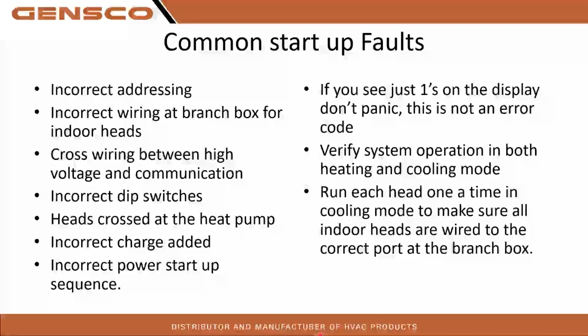Another one is the incorrect power startup sequence. I talked about that. If you see an LED or LCD display on your heat pump, and you're seeing just ones on that display, that is not an error code. Those are what we call status flags, and I'll show you what those mean in just a little bit. An actual error code is going to pop up as a 4-digit code on the heat pump: 4100, 4250, 7102. 7102 is a very common one that we see on startups. That's a code for total capacity of the system, either underconnected or overconnected. Usually when I see a 7102 on a new startup, it's because it's looking at underconnection. What people end up having issues with is incorrect wiring, cross wiring, power sequence, all those things can affect that. Condensate pumps on wall heads not wired up right, that kind of stuff.